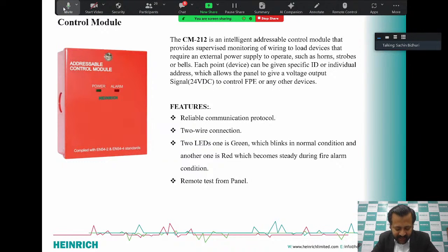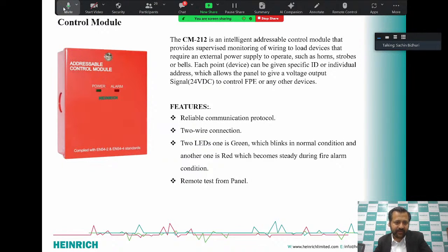As I told you, the point is, if there is a complete loop and the loop gets faulty or short circuit, the whole loop will get short circuit. But with the help of isolator modules we can install one after every 20 to 30 devices. Suppose there are 120 devices, so after the first 30 devices I have installed one isolator module, and after another 30 devices I have installed another. Suppose the short circuit happens in the second 30 devices, so only those 30 devices will not get power, but all the other 90 detectors or devices will be working fine with the help of these isolator modules.